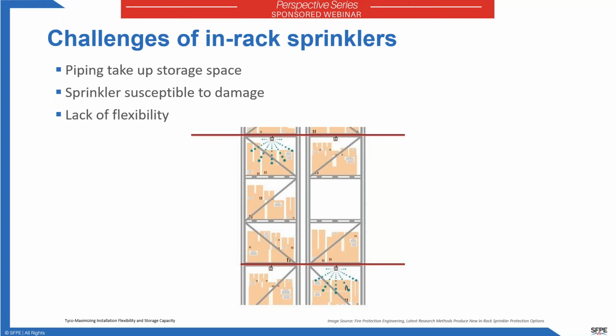And there are a significant amount of schemes available using in-rack sprinklers, both in NFPA 13, which now actually has a whole chapter, chapter 25, dedicated to in-rack protection schemes, and FM 8-9 also offers some alternative protection schemes as well. And in-rack sprinklers offer very effective fire protection.